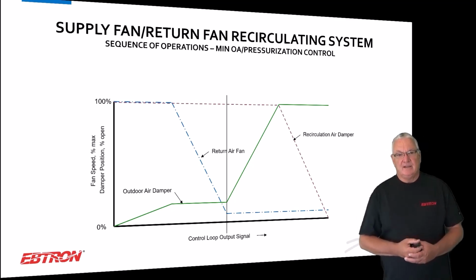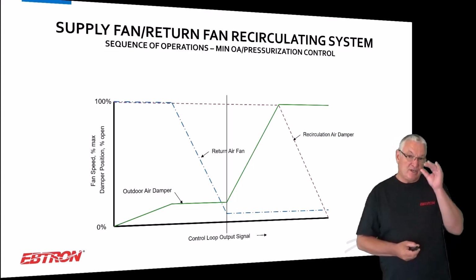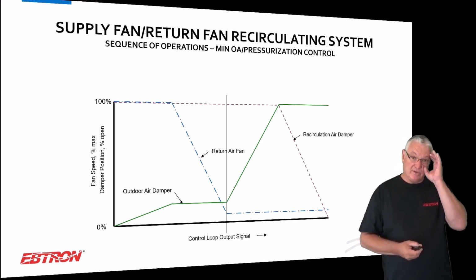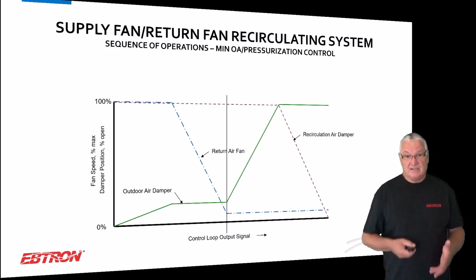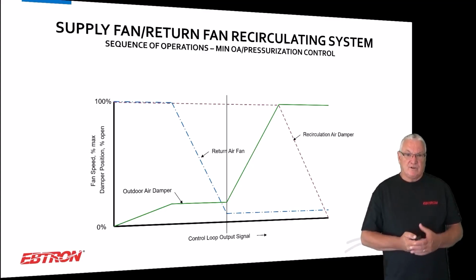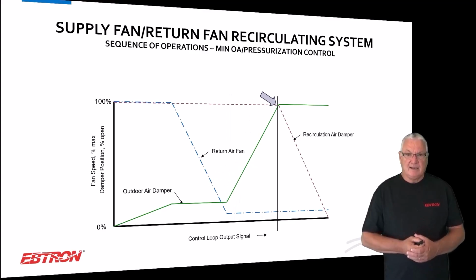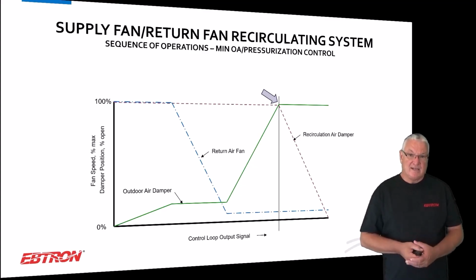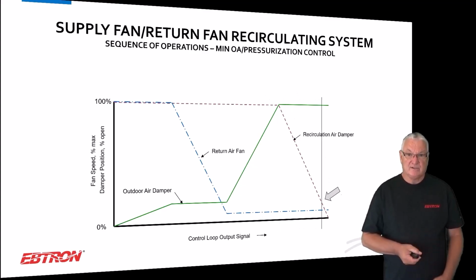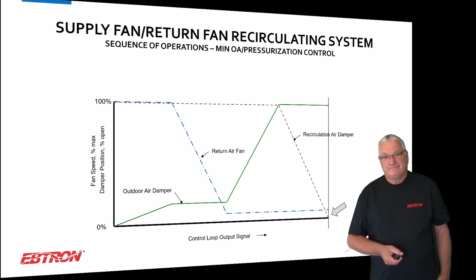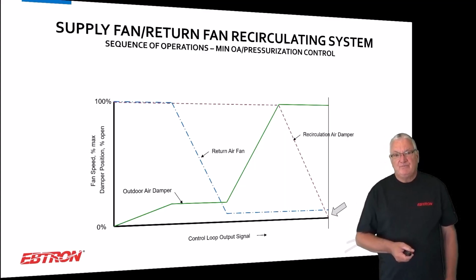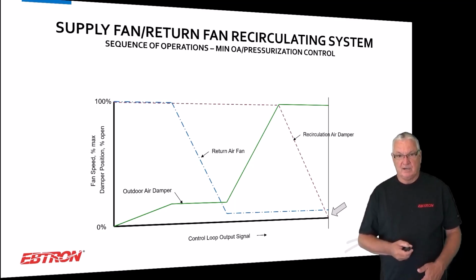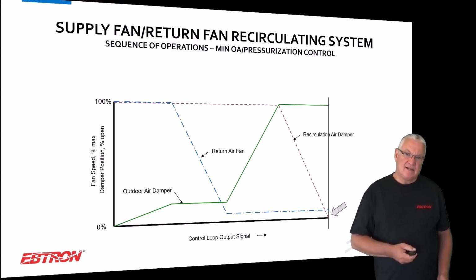On the other hand, if you didn't have enough outside air, which is possible, okay, so you have your return fan at its lowest speed and you're still not bringing in enough outside air, then you're going to first modulate open the outside air damper, and then if you still don't have enough outside air, you're going to modulate close the recirc air damper. If this is designed properly, you most likely will never be in that recirculation air damper part. Could happen with an undersized min-max.